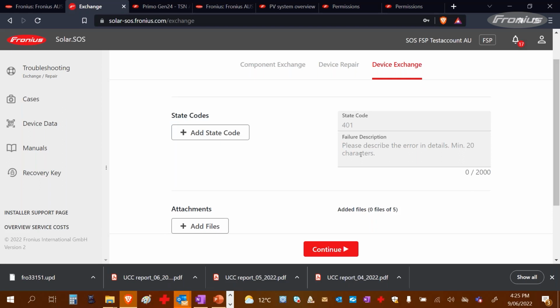So please enter the information that you have. I'm just going to put in megger test results. Verifying. Panel checked. Checked. No isolation fault found. Replace the inverter. So just a short description of what went wrong on site and a failure description would really help us a lot.